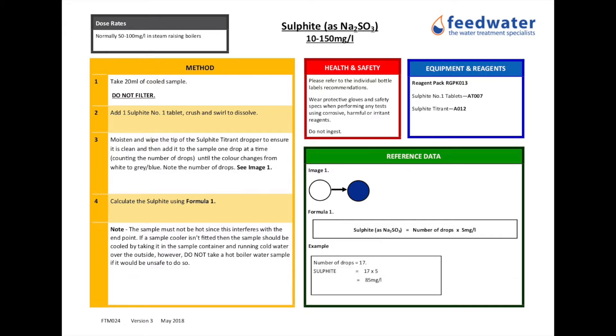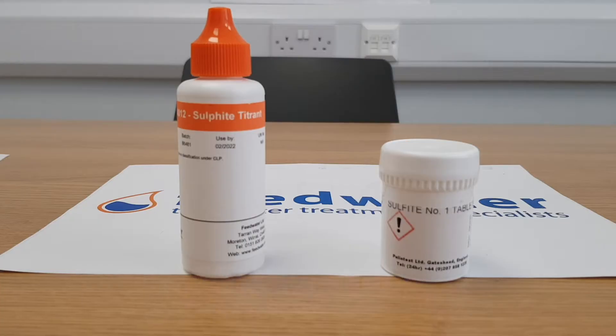Sulfite performs the vital task of oxygen scavenging, meaning it will remove dissolved oxygen from the water. This is important as any dissolved oxygen can lead to corrosion issues within your boiler.